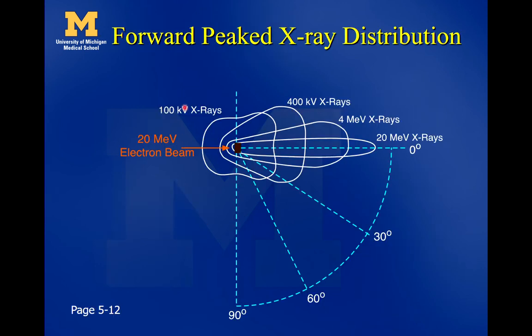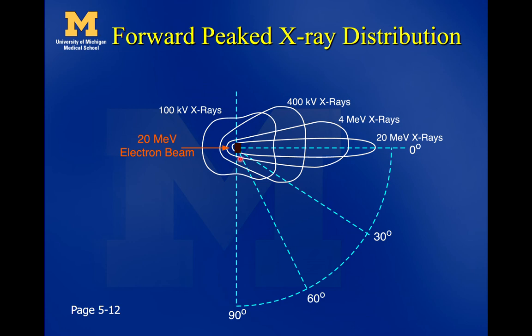Another aspect of these x-ray beams is that the distribution tends to be forward-peaked. For example, a 20-MeV electron beam making a 20-MV x-ray beam for radiotherapy produces x-rays from 20 MeV all the way down to zero — most at zero are attenuated away. In an angular intensity distribution, the 20-MeV x-rays mostly go straight ahead in the direction of the electron beam, while 4-MeV x-rays give a wider distribution, and at 100 kV it's much more evenly distributed.